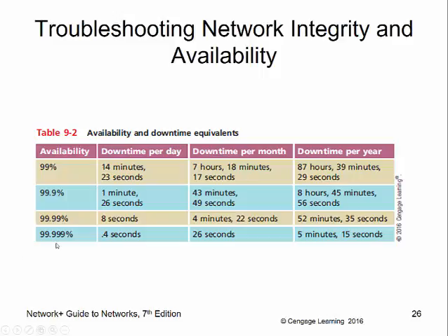Getting to 5 nines availability requires millions of dollars of infrastructure if you're doing it in-house. You're talking about building data centers on overlapping power grids. So just in case one power company loses their circuit, I'm on some other power company also. I'm getting fed by both of them. I'm talking about large enterprise UPSs, large diesel generators, redundant network connections, many different network connections coming in and out of the facility. This is achievable, but to achieve it, you have to have a real need for it to justify the expense of it.